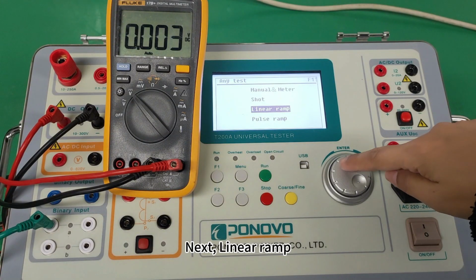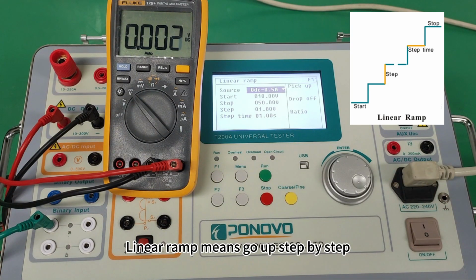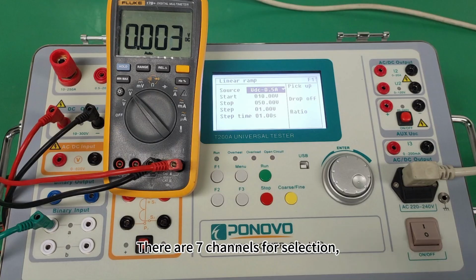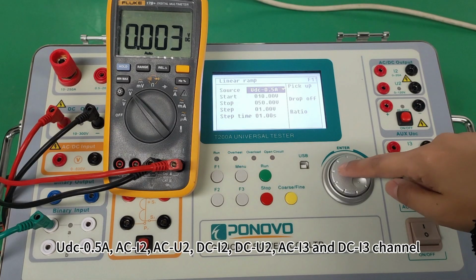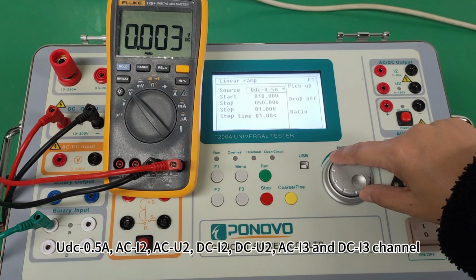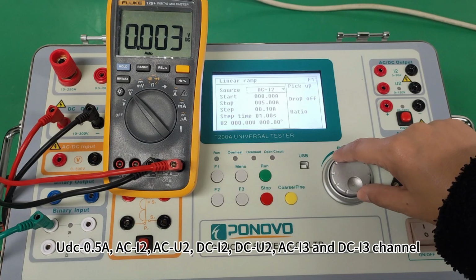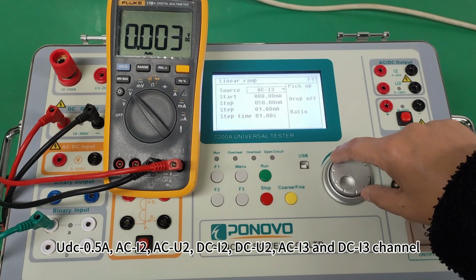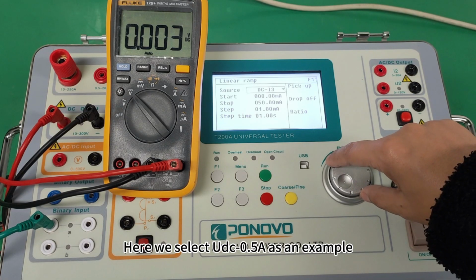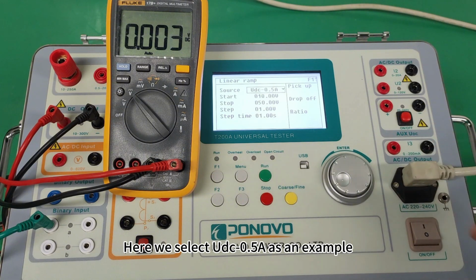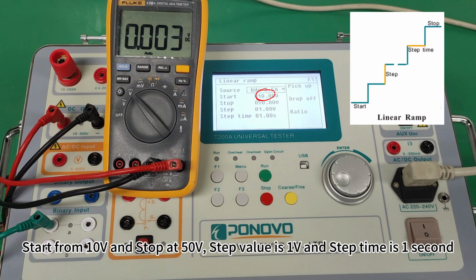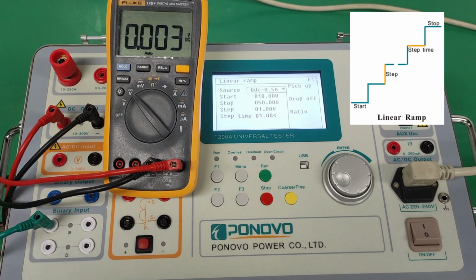Next, linear ramp. Linear ramp means go up step by step. There are 7 channels for selection: UDC 0.5 ampere, ACI2, ACU2, DCI2, DCU2, ACI3 and DCI3 channel. Here we select UDC 0.5 ampere as an example. Start from 10 volts and stop at 50 volts. Step value is 1 volt and step time is 1 second.